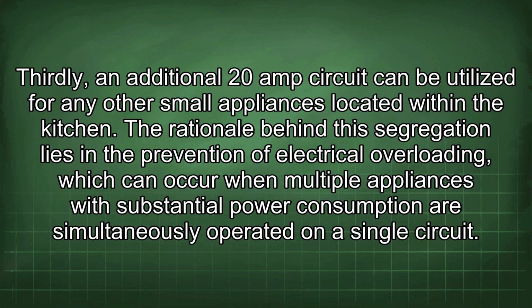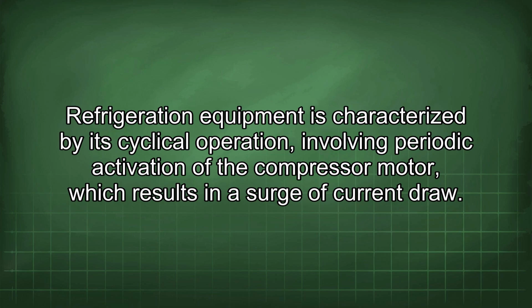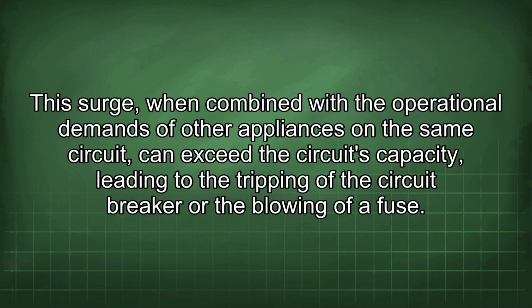This segregation prevents electrical overloading, which can occur when multiple high-power appliances operate simultaneously on a single circuit. Refrigeration equipment operates cyclically, with periodic activation of the compressor motor causing a surge of current draw. This surge, combined with other appliances on the same circuit, can exceed the circuit's capacity, tripping the breaker or blowing a fuse.